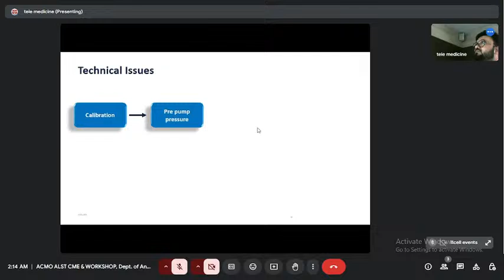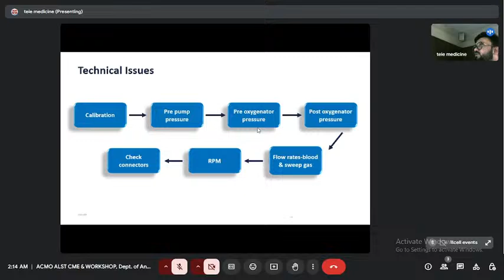And after that, you have to check the pre-pump pressures and go for the pre-oxygenator pressure, P2. This is P1, P2 and P3. What is the change between them? Delta pressure. And see the blood flow and sweep gas rates. And see the RPM. And check the connectors, whether there is any leak and all those things.